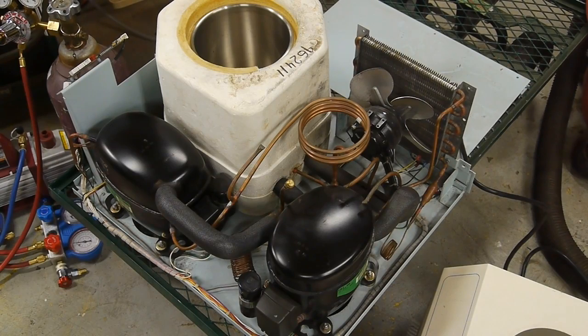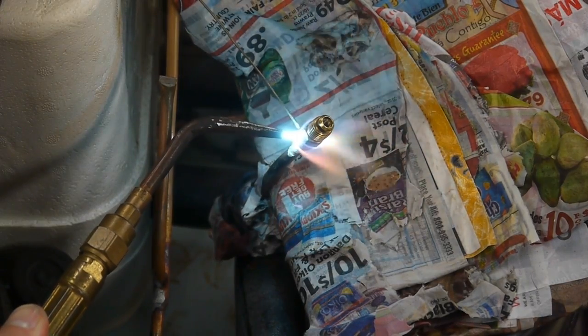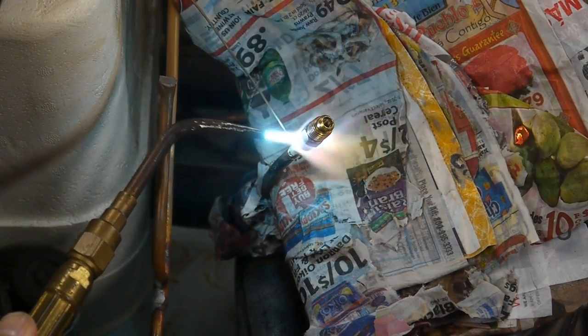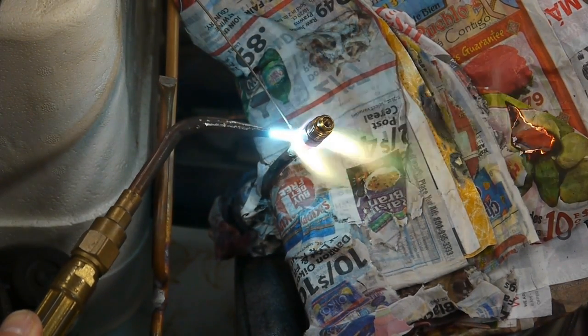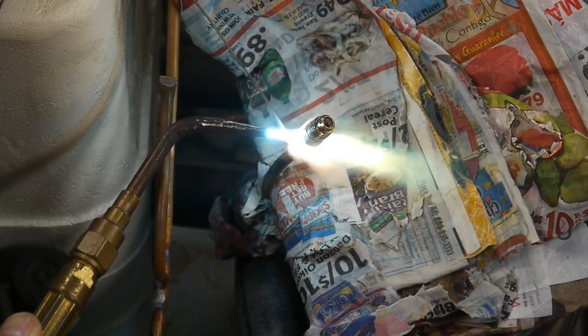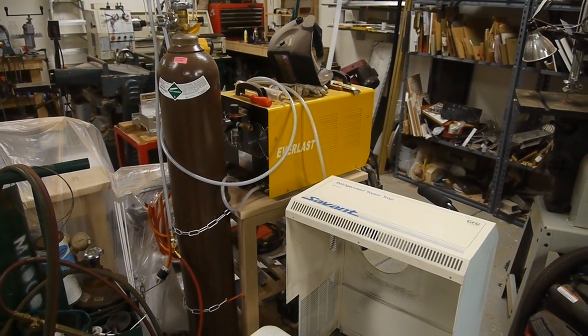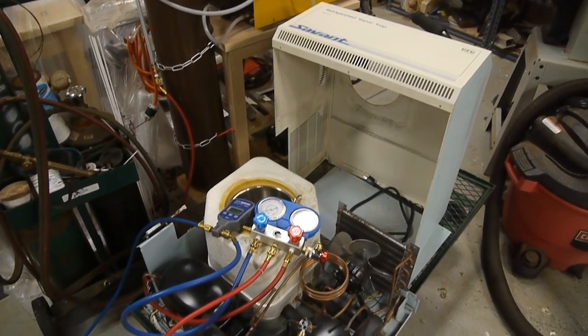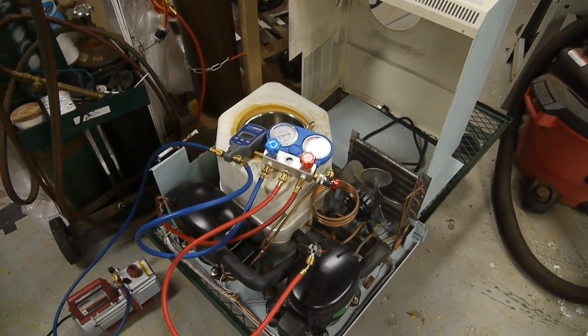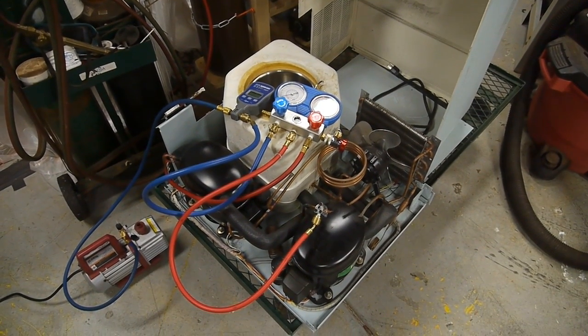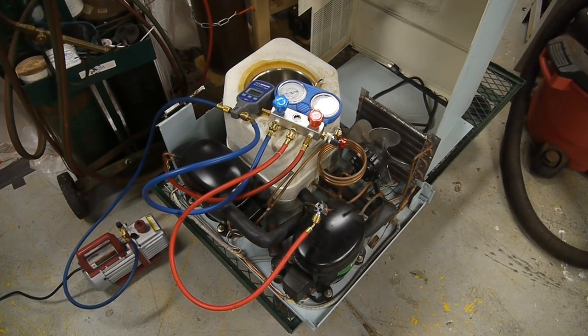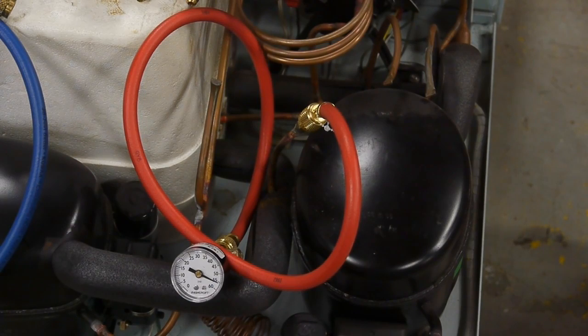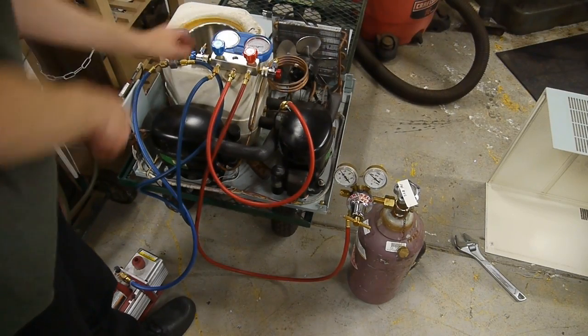Second, since I wanted to do hot work on the system and solder on a new fitting, I wanted to get that flammable gas out and replace it with argon. So I hooked the system up to my manifold and pumped it down with a vacuum pump, then filled the system back up with argon and let it sit at about 40 or 50 psi for a day or two just to see if there were still any remaining major leaks.